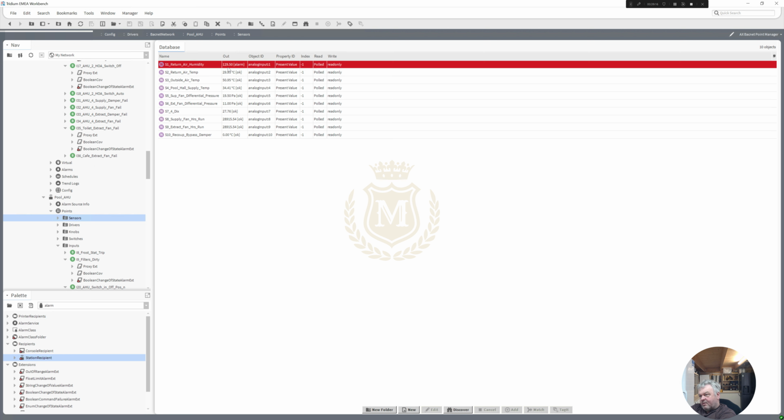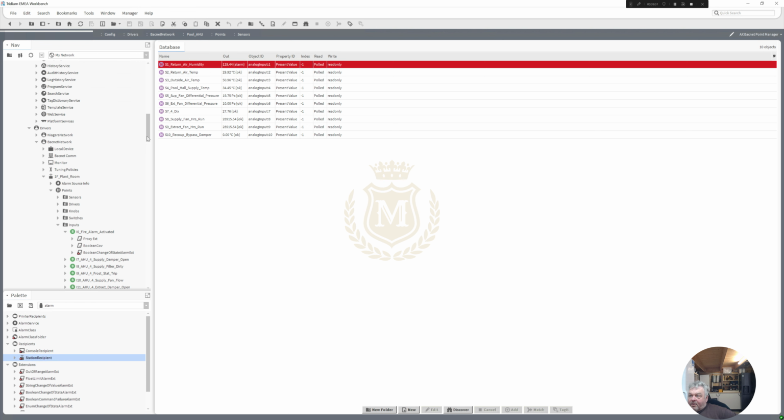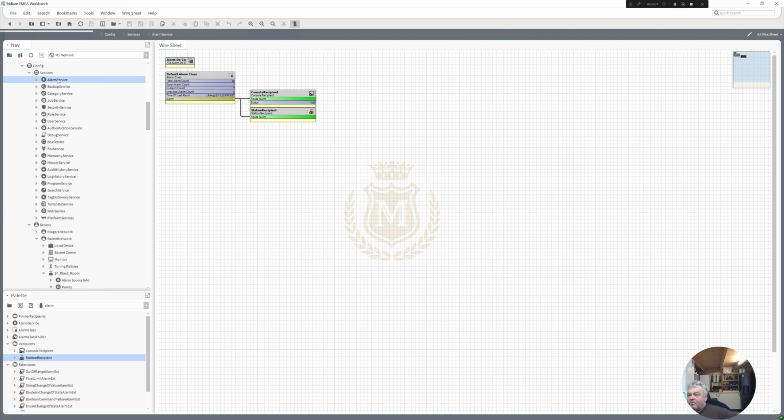If it's a pool, it should be 52, 55, 60 maximum percent RH. So I'm going to go with that one, and I'm going to keep that in alarm until I'm not going to remove an alarm off it. So we've done that. Send it to the station.